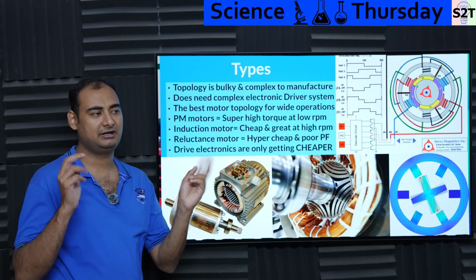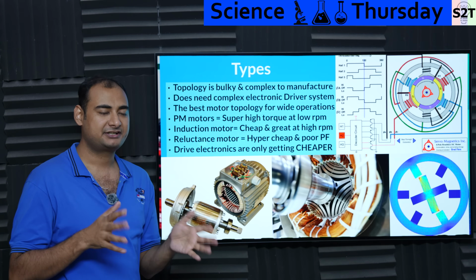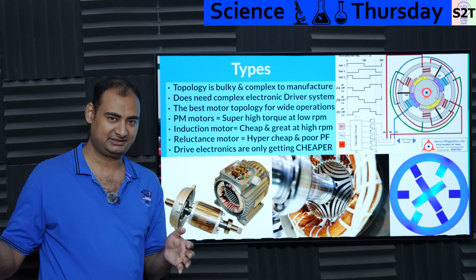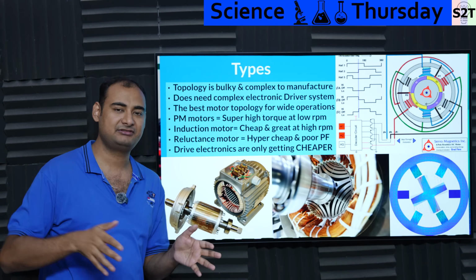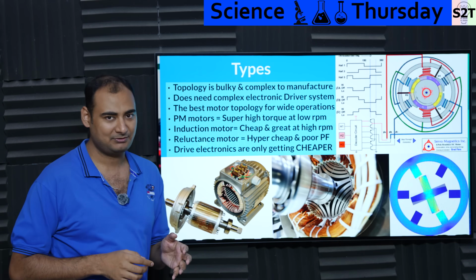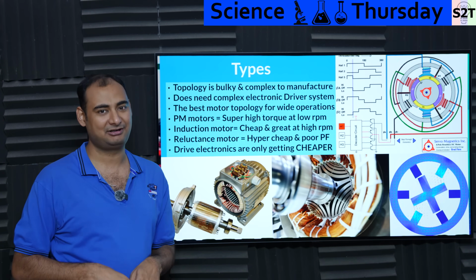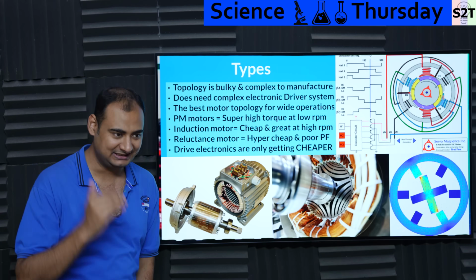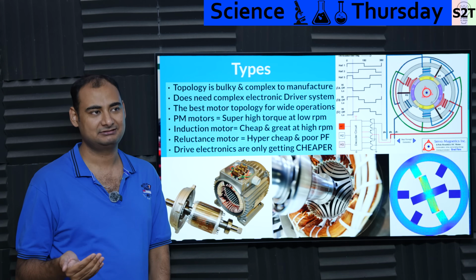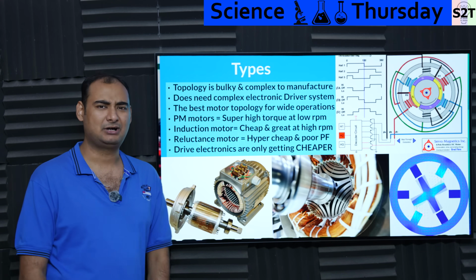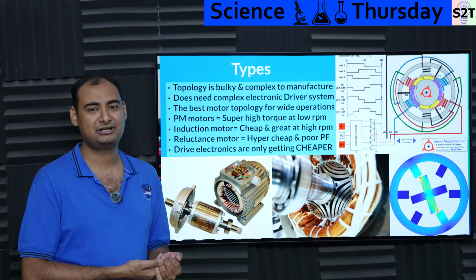You might ask, why not have power factor correction? Power factor correction protects your downstream things - say there's a transformer, your VFD will protect the transformer from poor power factor, but the VFD still has to deal with the power factor itself. It doesn't disappear. You inherently want there to be no power factor correction requirement. And how the heck can an induction or synchronous motor do that?